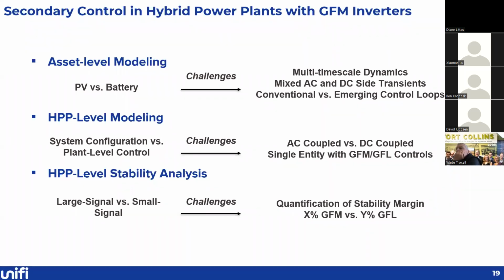For the HPP level modeling, we also need to consider the system configuration as well as the plant level control, the HPP level control. The HPP is a little bit similar to the conventional microgrid, but it is not exactly the same. The reason is we may have, for example, an intermediate DC bus to couple the DC-DC converter stages of the PV inverters and the batteries. In the meantime, we may have multiple parallel DC to AC inverters to interface the DC bus and the AC bus, so the configurations could be not exactly the same.